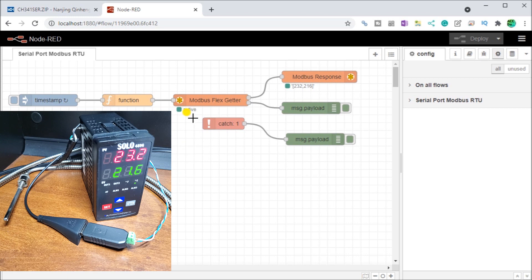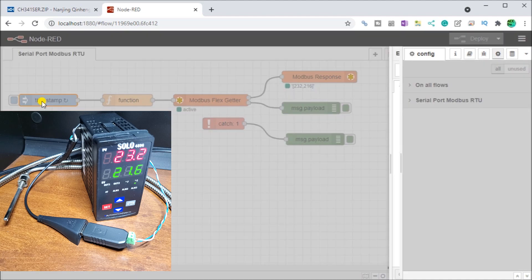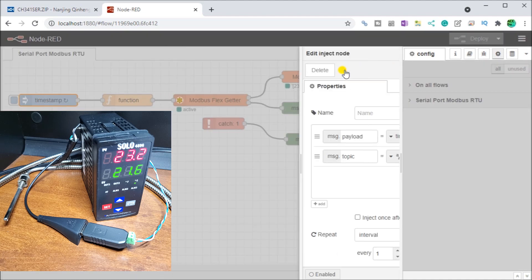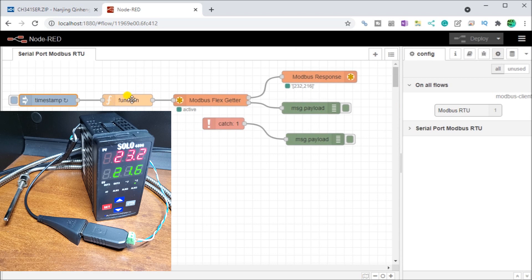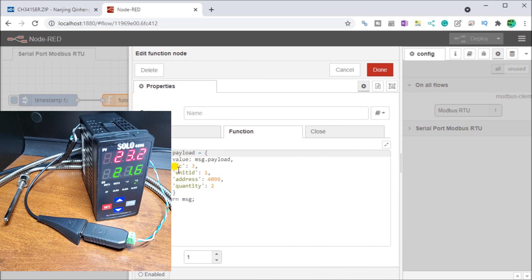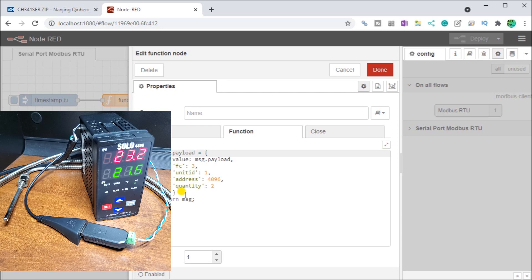So that is our configuration. And in here, you can see that what we're doing is every second we are asking for information through our command function. So this is multiple read. This is a unit ID one, which is a solo. This is the address, which is 4096. And we're asking for two of them, giving back, giving me the present value and the set value of our process temperature controller.